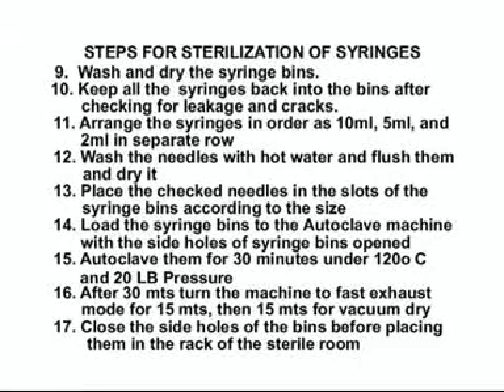Place the checked needles in the slots of the syringe bin according to the size. Load the syringe bin into the autoclave machine with the side holes of the syringe bin opened. Autoclave them for 30 minutes at 120 degrees centigrade, 20 lb pressure. After 30 minutes, turn the machine to fast exhaust mode for 15 minutes. Then 15 minutes for vacuum dry. Close the side holes of the bins before placing them in the rack of the sterile room.